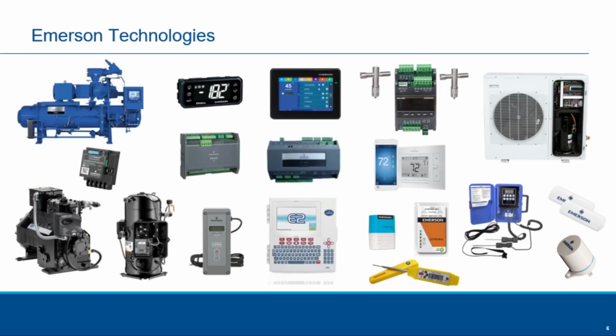When the compressor's running, that superheat valve, how is it maintaining superheat? It can connect to our X-line unit that I'll talk about in a second. And if you get any alarms, it's going to send an alarm right to your cell phone. Right? This is under our ProAct division, so you can log right in from your cell phone or from your computer. There's value in that because you can see what has happened to that system when you weren't there.